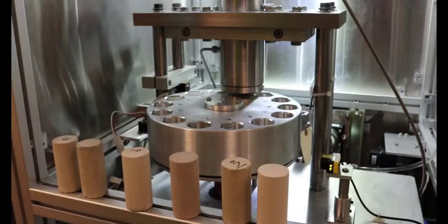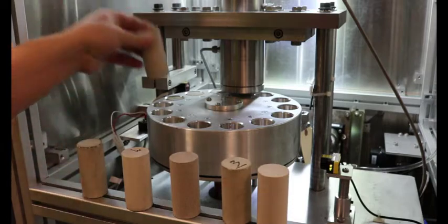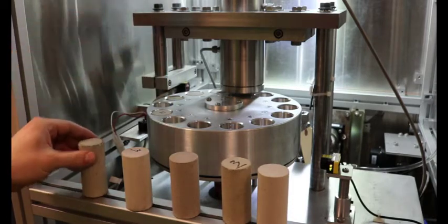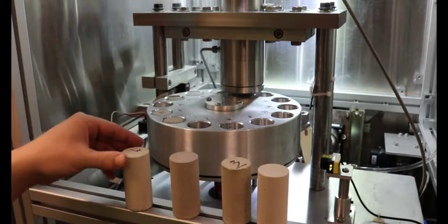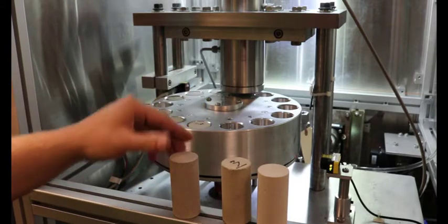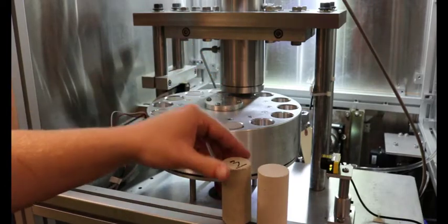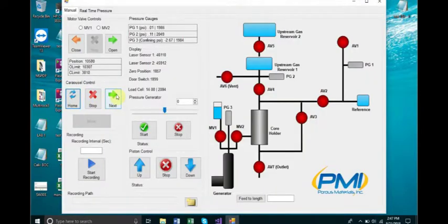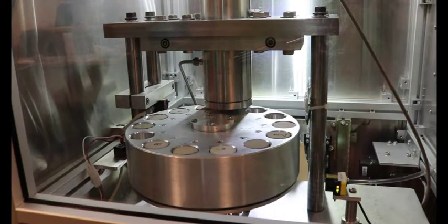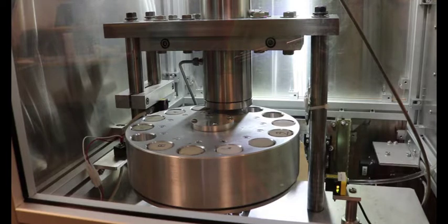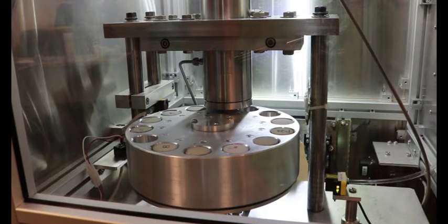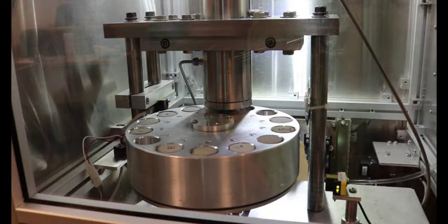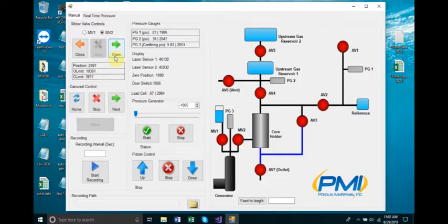We will now instruct the user to operate the APDP-HP101 using manual controls. Ensure the reservoir bottle is filled with water. Place the rock samples in the carousel, beginning at the first slot and continuing in ascending order until all samples are in place. Starting from the main menu, click the manual control button. This will bring up the manual control window. Then click the home position button to rotate the carousel and align the first sample with the core holder. Ensure slot number one is aligned at the base of the core holder. Click the up button from the manual control window to load the sample into the core holder. The screw jack will stop once the sample reaches the top of the core holder.